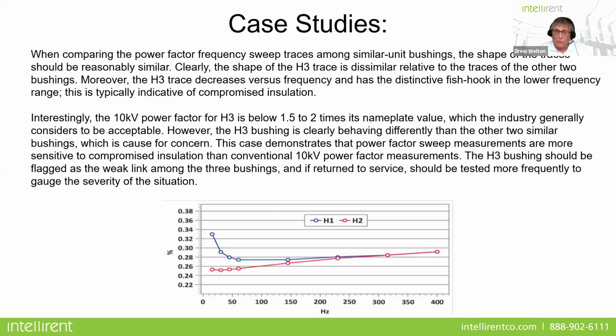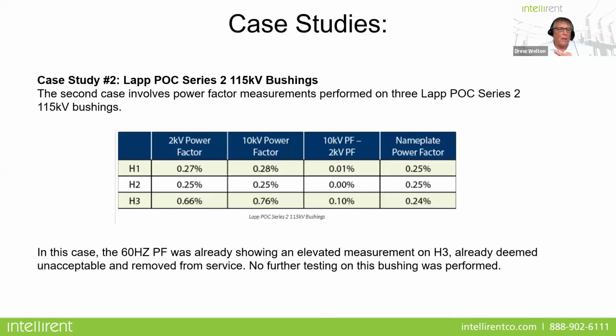And if you're going to return it to service, it should be tested more frequently to gauge the severity of the situation. Okay, so here's another case study that was done on a Lapp bushing. In this case, the 60 hertz power factor was already showing extremely elevated measurements in H3. So we knew that one's got to go. All right, but let's take a look at the other two.